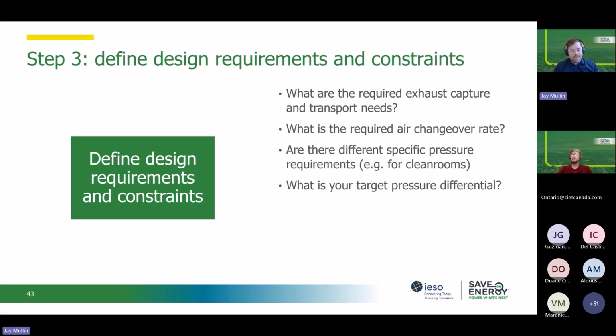The next step is to define your design requirements and constraints. So, what are the required exhaust capture and transport needs? Like if you have that paint booth, what is the minimum capture velocity of the airflow across any openings that you need to have? What is the required air changeover rate for your facility, for your operations? Depending on what you're doing in your facilities, these might be prescribed by industry standards or regulations.